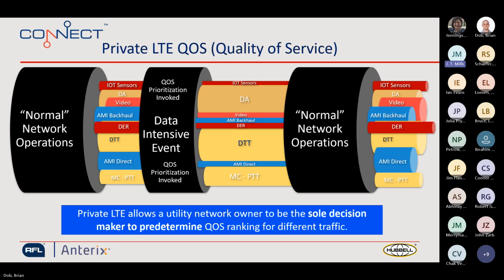For example, a storm comes through, your storm flag comes up, you want to get all your recloser data, DA data from all your points at 100% reliability. And you're able to shape your traffic to make sure that that is first, high reliability, and you get your lowest latency on all. At that same time, AMI billing data, you don't need that information congesting the system, congesting the pipe. So you deprioritize that data. And that data sits in a queue. It'll come back after your event, right? The data doesn't disappear, but it just sits in and gets deprioritized.